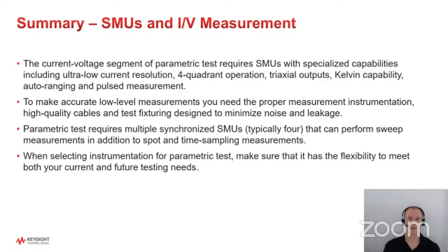So the key points of what I've talked about so far are really these 4 points shown here. Again, as I said, SMUs used for parametric test really do have special needs. They have to have special capabilities: ultra low resolution, 4-quadrant operation, triaxial outputs, 4-wire or Kelvin measurement capability, auto ranging, things like that. Also, to really make good low-level measurements, you need other parts, not just the instrumentation: good cables, good test fixturing, a quality wafer prober if that's what you're doing, things like that.